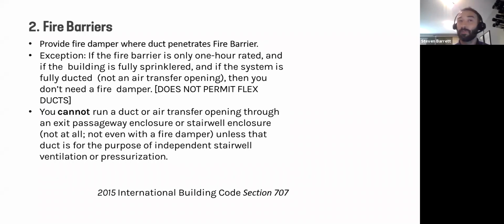It's obviously very popular, very common on projects to have flex ducts. And this is something that gets missed a lot on projects, but technically, this exception does not work if you utilize a flex duct as part of your system.